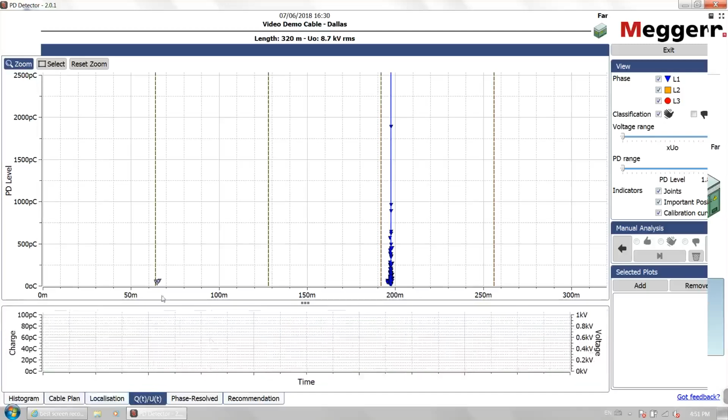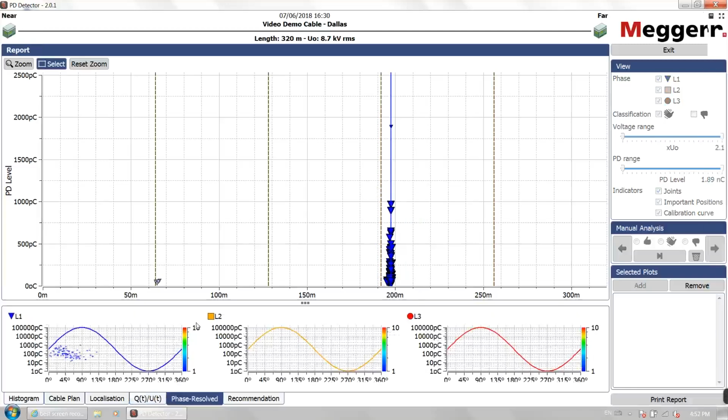Q(t)/U(t), basically this is our, if I highlight some events here, we'll see that these are heavily biased towards the positive polarity, but that's kind of expected with damped AC, especially the way we noticed that all of our first cycles were positive polarity. So if we wanted to be thorough, we would run an equal number of positive and negative polarity damped AC cycles to even this out. So the way we did the test, this might not be very significant.